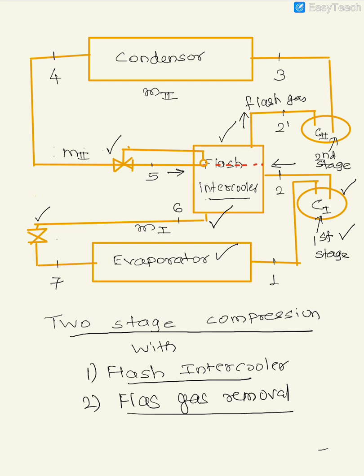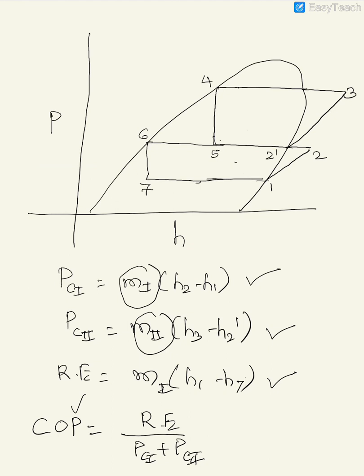The refrigerant emerging out from the evaporator at state 1, as you see here, gets into the first stage. It is compressed in the first stage and then intercooled in the flash intercooler. The refrigerant would then enter compressor 2. This will be more clear when we look at the pH diagram — the compression happens from 1 to 2.